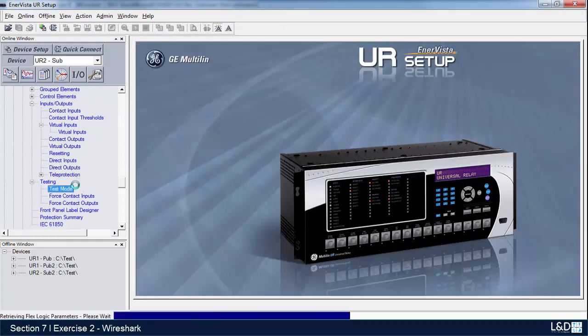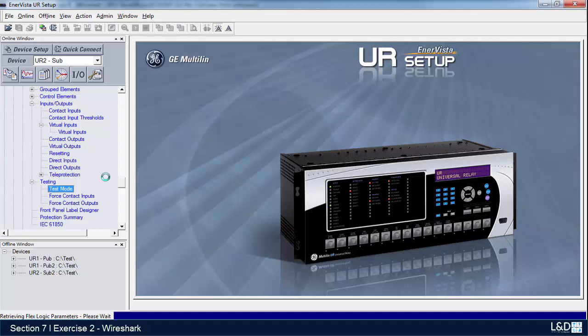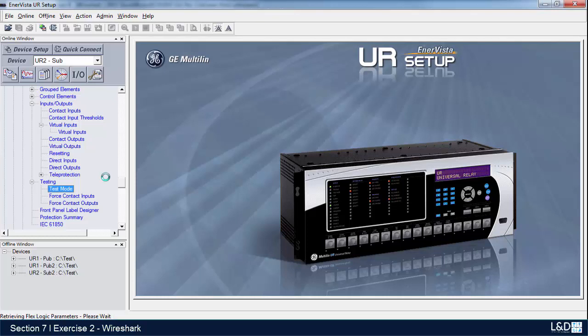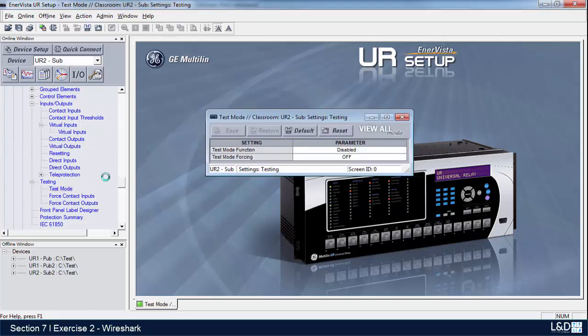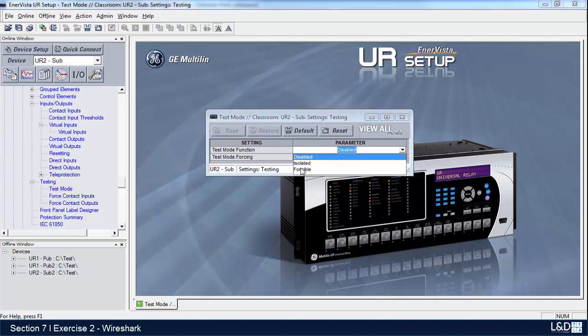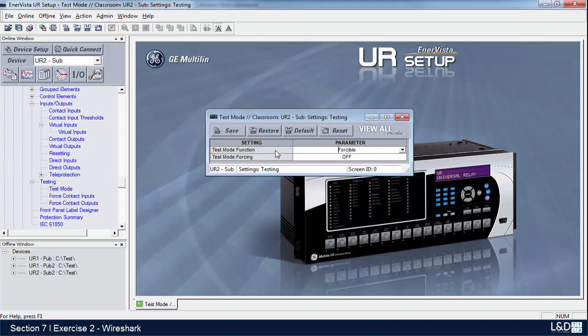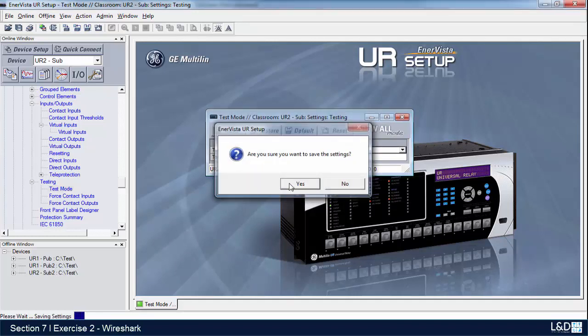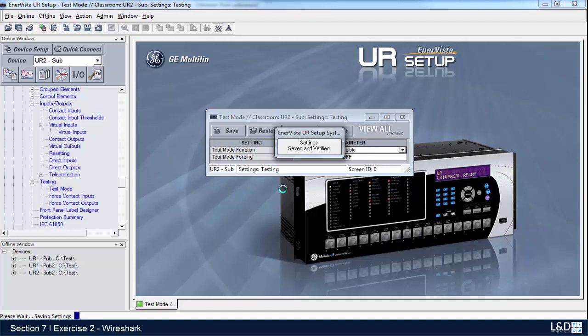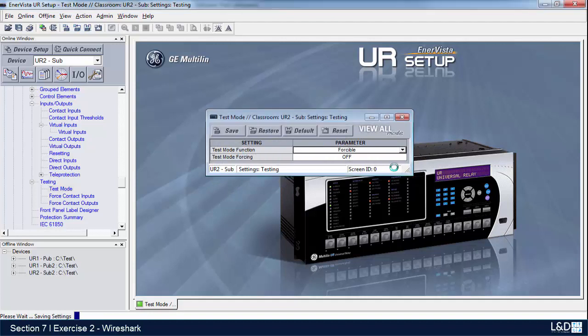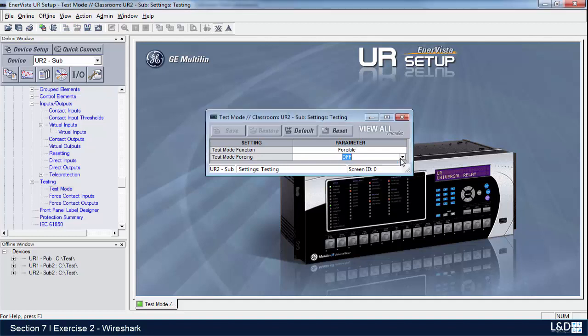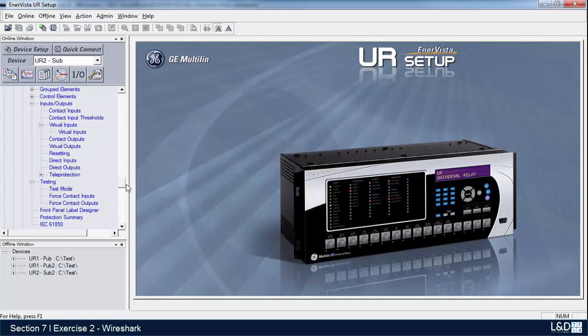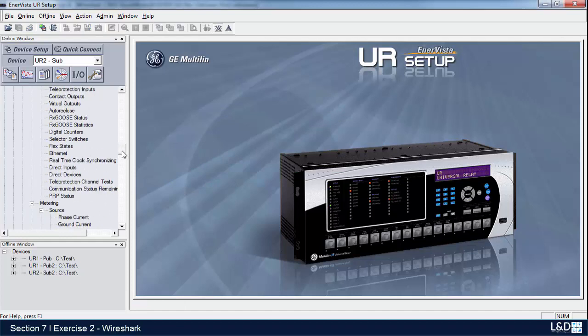I'm going to test mode, and we'll switch on test mode on both. What does test mode do? It blocks the output relays from energizing. So test mode, we've turned it to forcible, and let's do the same thing to the other side.